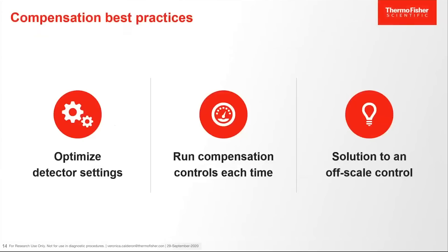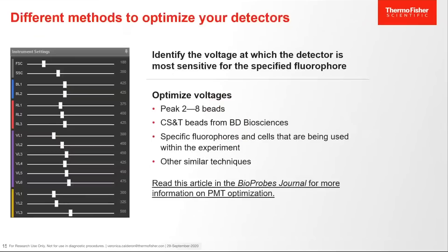Looking at compensation best practices, remember to optimize detector settings, run compensation controls each time, and there is a solution to an off-scale control. Optimizing detectors involves identifying the voltage at which the detector is most sensitive for the specified fluorophore. Voltage optimization can include Peak 2-8 beads, CS&T beads from BD Biosciences, specific fluorophores and cells being used within the experiments, and other similar techniques. More information can be read at the provided link, and these methods can be used across any instrument.